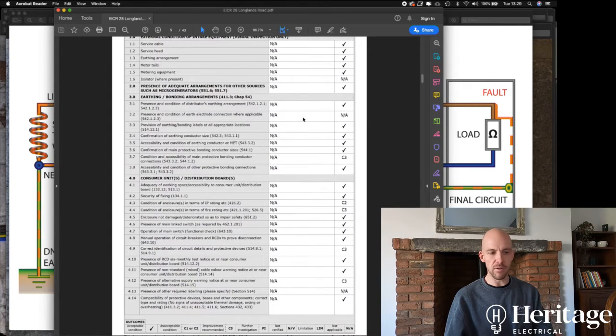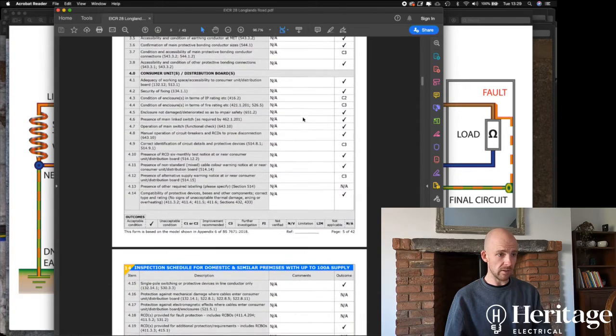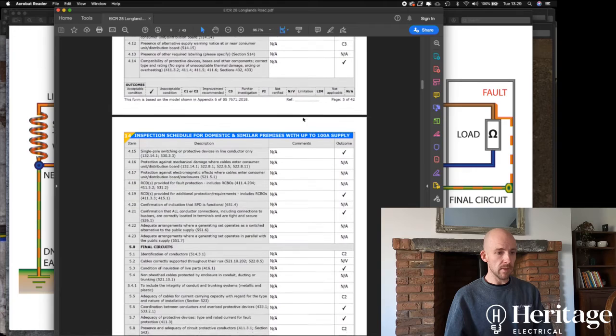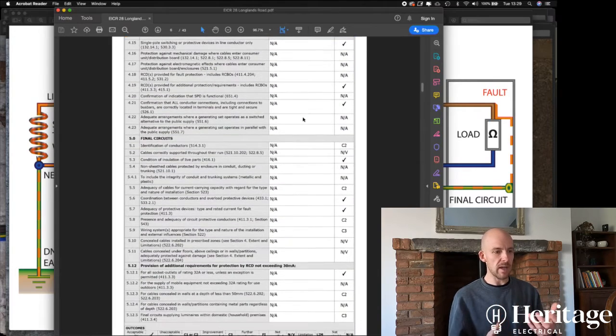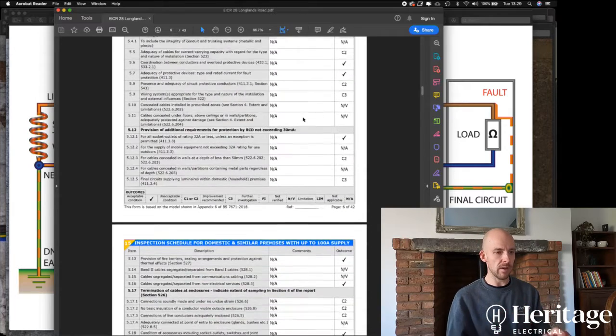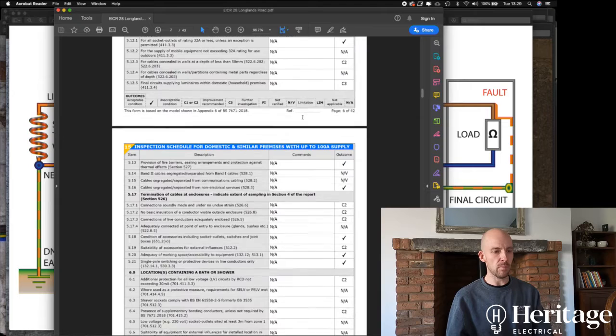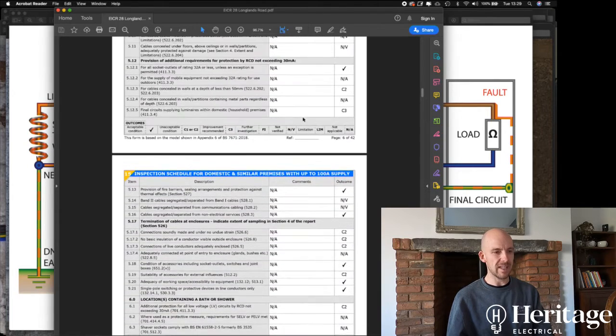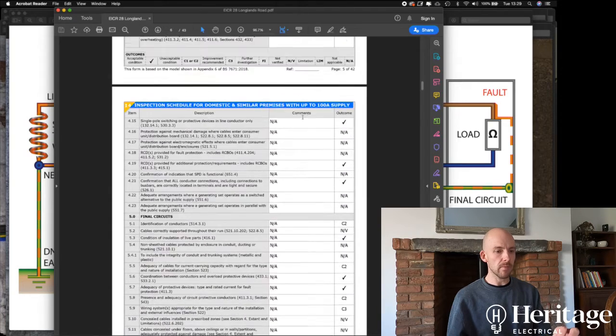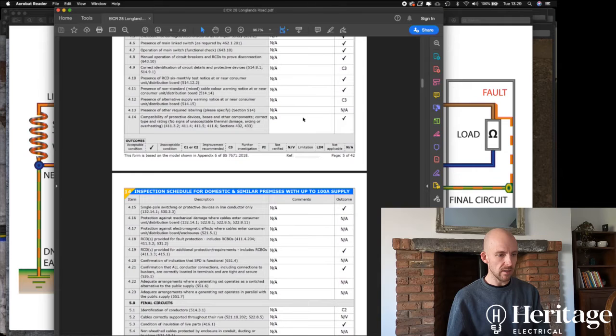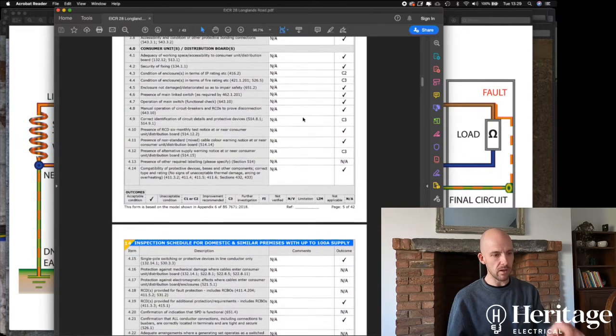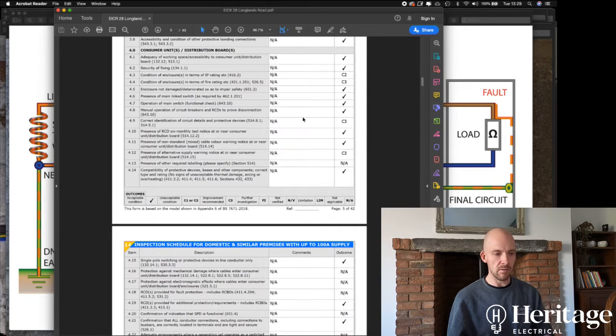Thereafter, and I'm not going to go through all these, you can see there's a huge list of inspections. Some of these are informed by taking things to bits and having a look behind and having a look at the cables and what have you. Some of these ticks or codes are informed by the test results that we obtain when we're actually testing rather than inspecting. You can see at the end of each point there is a regulation code. So if we really wanted to, let's say for argument's sake, presence of a main linked switch, the red switch that we talked about before, we can go into the regulations. So does it have presence of a linked main switch in the consumer unit?